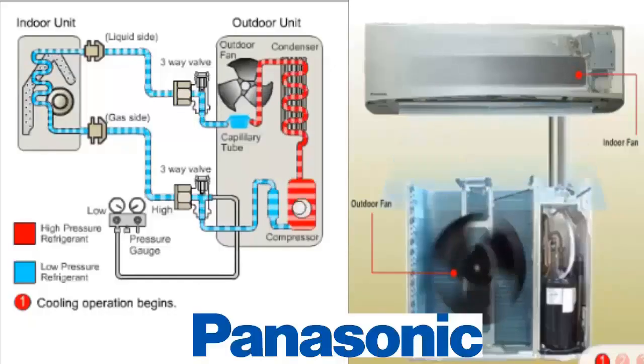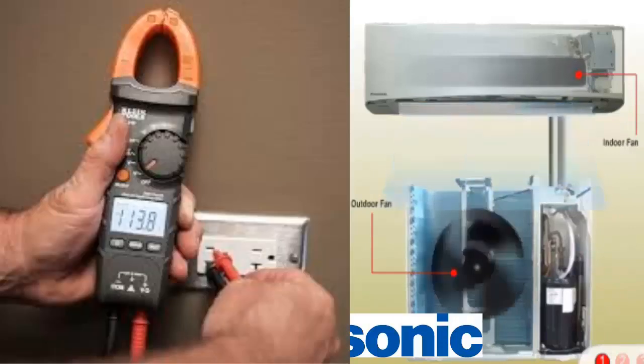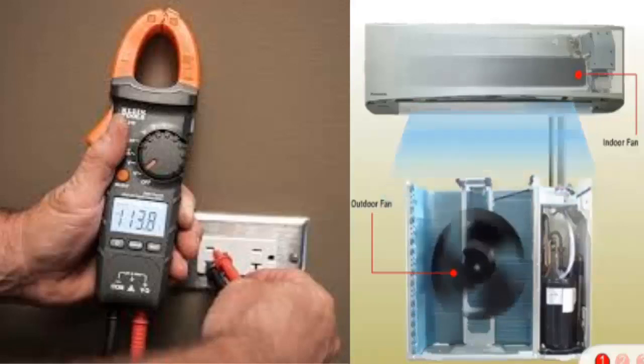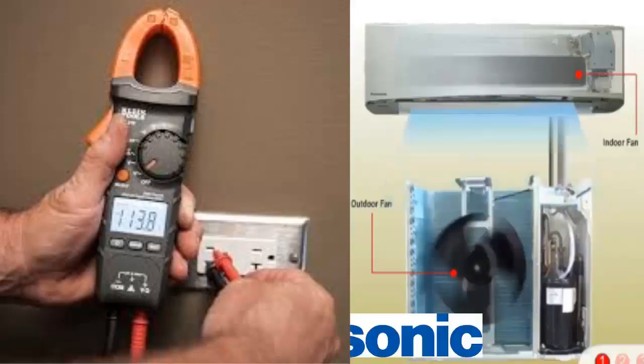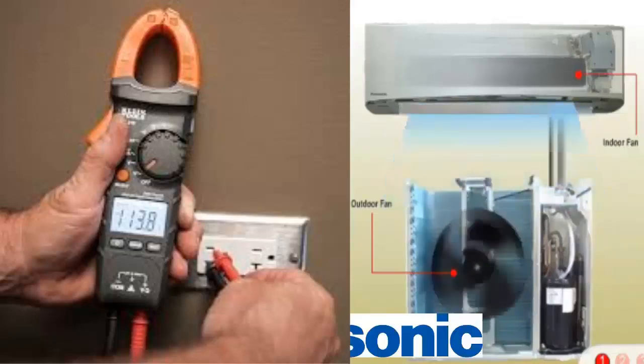4. Supplied voltage. Verify that the voltage provided by the electrical supply is adequate because low voltage can cause the compressor amperage to rise to compensate for the lower voltage.